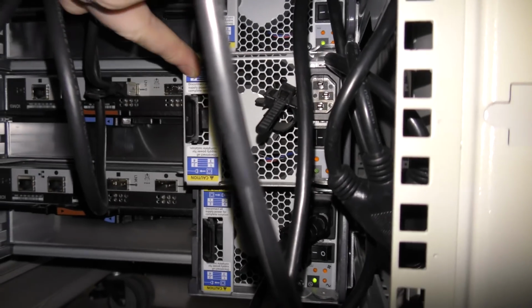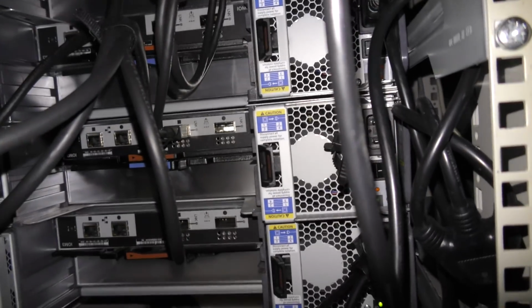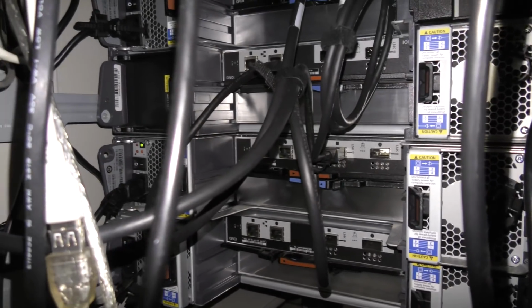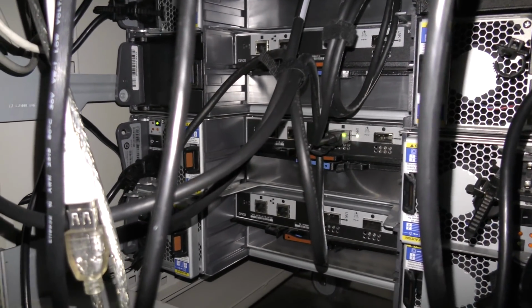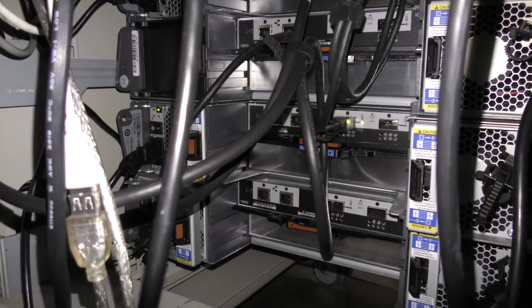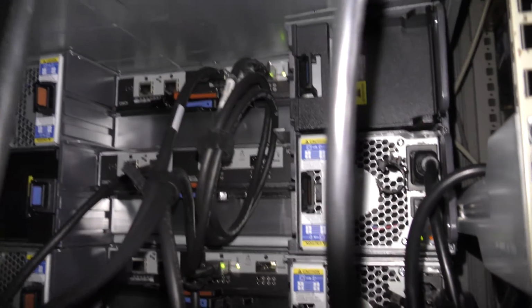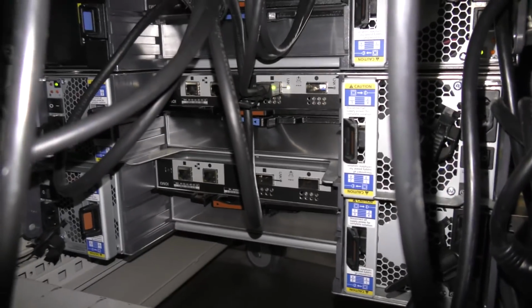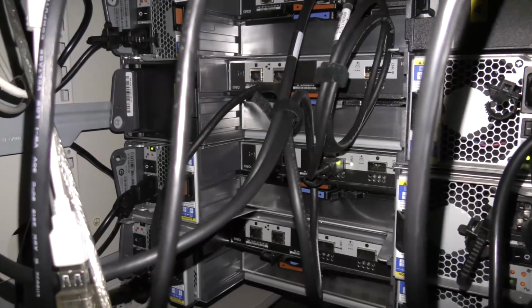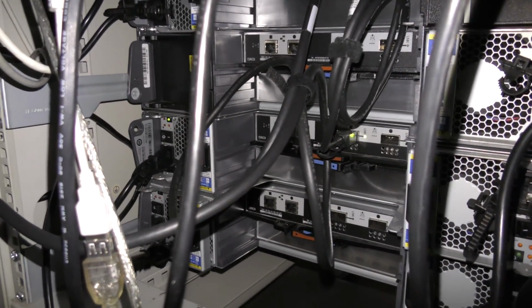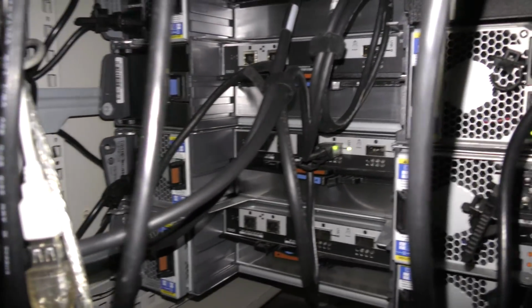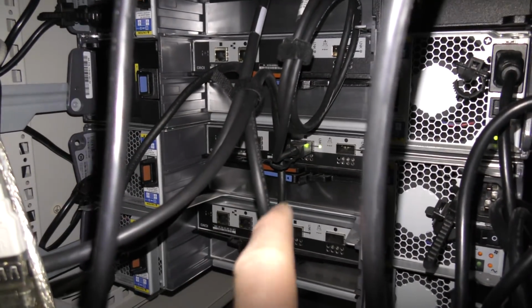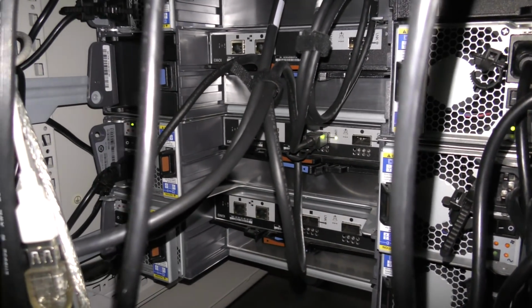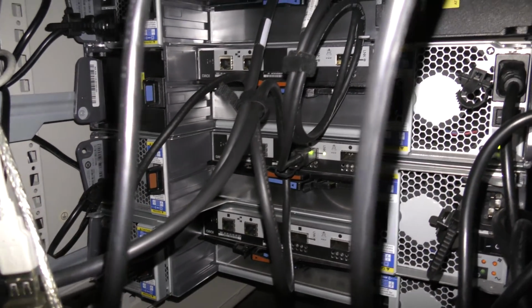You will notice that I have some of the power supplies that are not plugged in. I'm just using two power supplies in each of these shells. That should be sufficient. The top one does not even have four power supplies. It's only the bottom one that has four power supplies. An idle power supply does use power. That's also why I'm only using one of the two controllers, just to not have it use as much power.